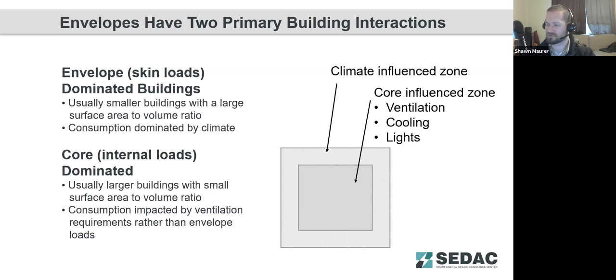Larger buildings, most commercial sites, will be core-dominated buildings, where the perimeter rooms and locations in the building will be impacted by envelope loads, and the core of the building is going to be primarily impacted by ventilation, cooling, and lighting loads. Because of ventilation in those spaces, it's still closely linked to environmental conditions, as conditioning ventilation is one of the primary energy components for HVAC systems. But it's important to note that for core-dominated buildings, the envelope loads themselves are a smaller proportion of the overall building loads as compared to envelope dominated buildings.